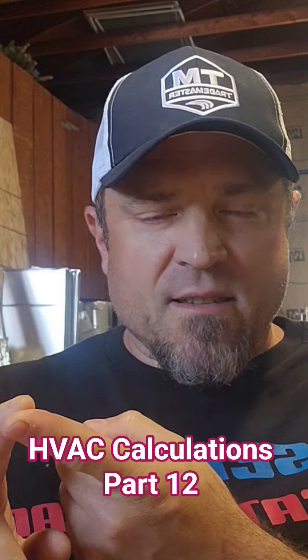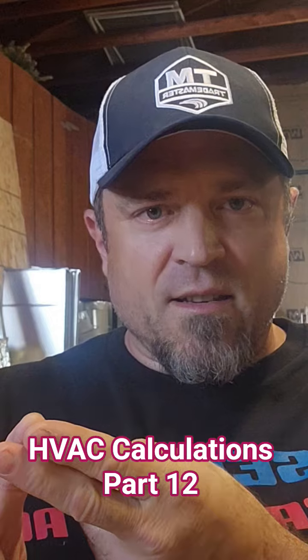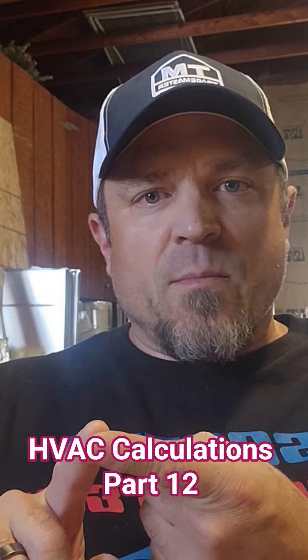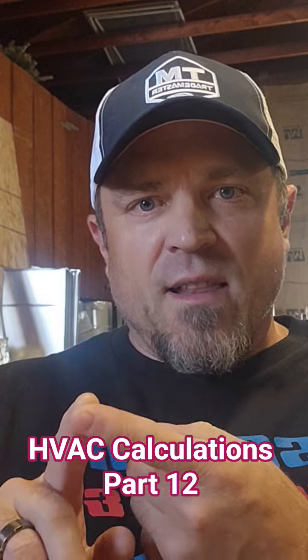Obviously, if it's new construction, which I don't do much of, I'm going to size the system first, then size the ductwork based on that. But I always use multi-stage variable capacity equipment, and I might even oversize the duct a little bit because I'd rather have less velocity than more, especially in someone's home.